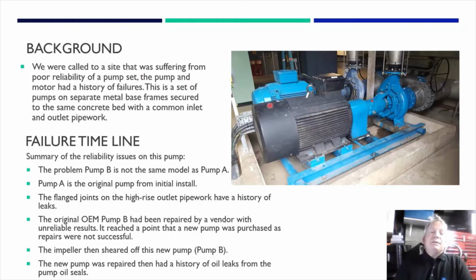We were called to this site for low reliability on the pump, so it's a metal frame, we have pump A and B. You can see this motor has been changed out because some repair company was changing it and it kept failing. Because it fell within the warranty period, they get smashed with warranties. In the end, the repair company said, look, here's a brand new motor, we're off. They just went through a repair cycle and didn't work out why this was happening.